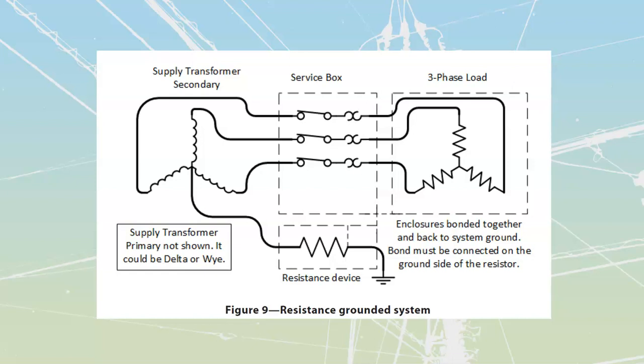So on high voltage systems, we use this type of system, because the resistance or impedance we have is going to limit that current down to small values. As soon as it's a small value, we get only a tiny arc. It might be a bright arc, but it's going to be much smaller, without the same watts or arc flash incident energy, AFIE. We'll do that through a neutral grounding device, which could be inductive or resistive.